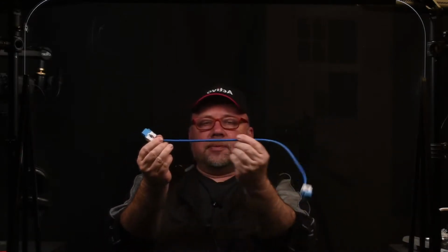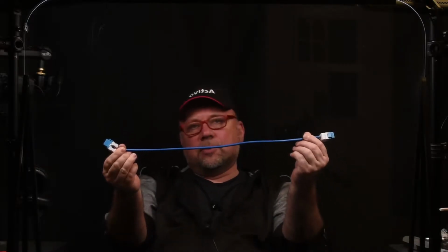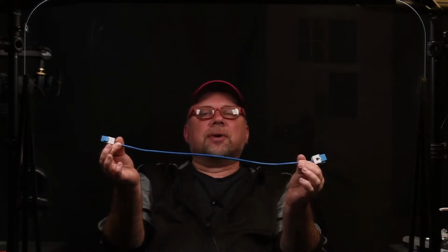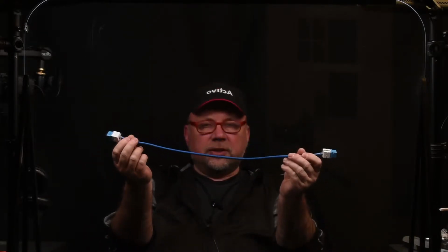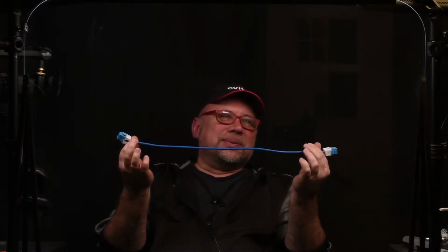Basically at the patch panel we have a female jack, and at the desktop we also have a female jack, and this wire goes in the walls, in the ceiling, in the raceways, in the cable trays, whichever way it goes, it makes itself to the other side of the data run. Now, how long can the wire be?